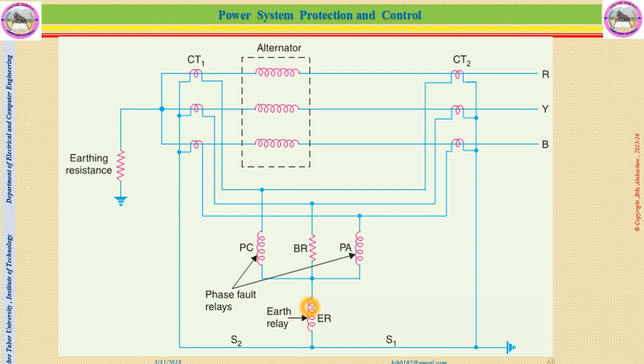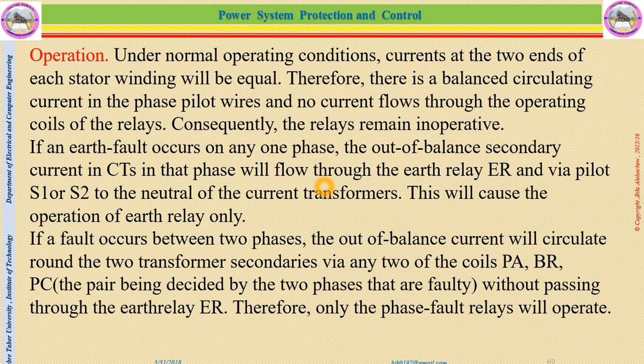Now, if a phase fault happens, there is no connection to this earth relay. For example, if this phase and this phase are shorted, the circulating current passes in such a way that there is no current which may pass through the earth relay. So this earth relay will be used only for earth faults.